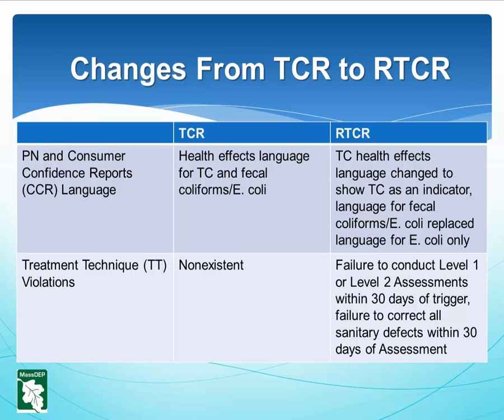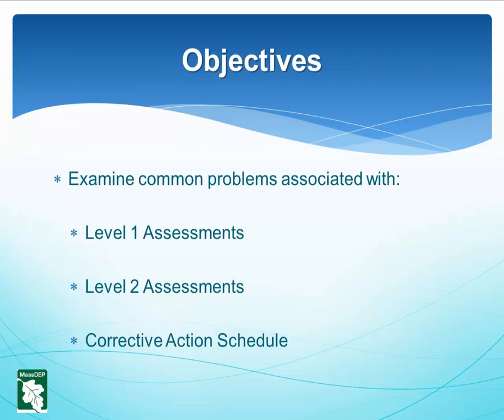In the TCR, there were no treatment technique, TT, violations. In the RTCR, since there are now Level 1 and Level 2 assessments, there are treatment technique violations for failure to conduct Level 1 or Level 2 assessments within 30 days of an assessment trigger, and failure to correct all sanitary defects within 30 days of assessment after you are made aware of the defect. Today's objectives. Let's examine common problems MassDEP has seen with Level 1 assessments, Level 2 assessments, and corrective action schedules.